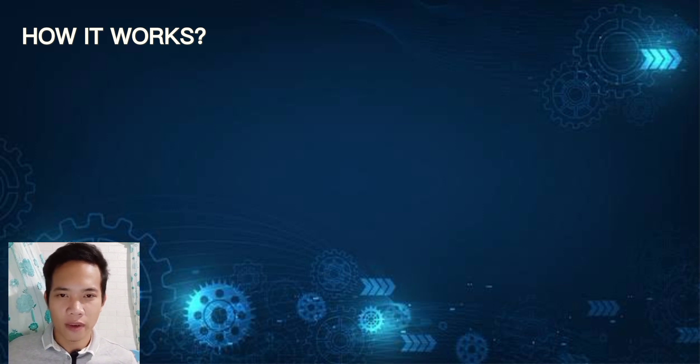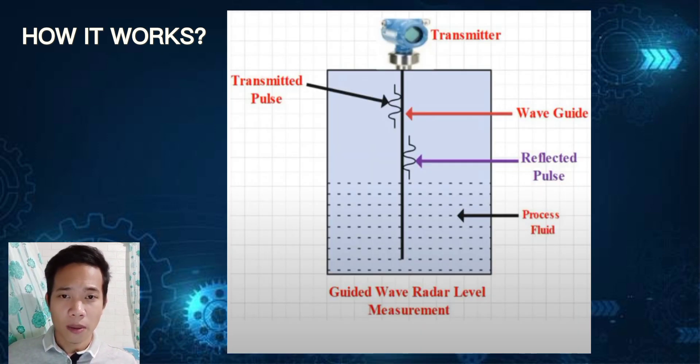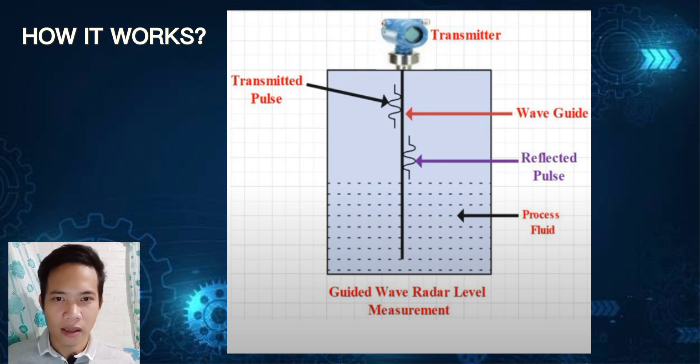How does the guided wave level sensor work? The microwave signal is sent down to the waveguide probe and travels along its length. When the microwave signal reaches the surface of the material, it reflects back towards the electronic unit.